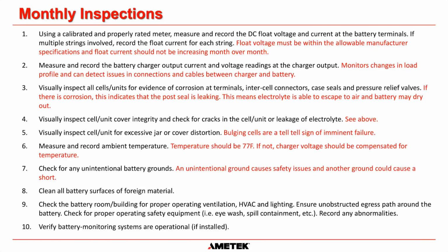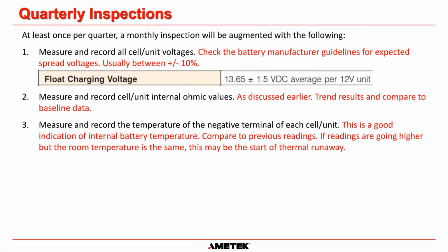And then during the monthly inspection, you want to clean all the battery surfaces of any foreign material. You want to check the battery room for proper ventilation, HVAC and lighting. Ensure there are unobstructed egress paths around the battery. Check for eye wash and spill containment if necessary. Obviously, for a valve regulated battery, spill containment may not be required. Record any abnormalities, and then verify that the battery monitoring systems are operational if they are installed. So that's the expectations for a monthly inspection.